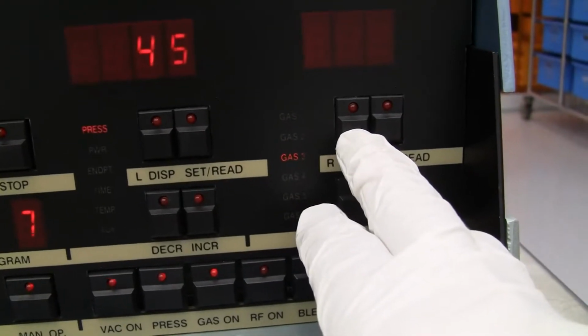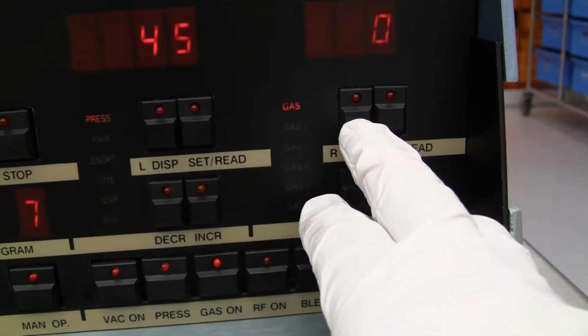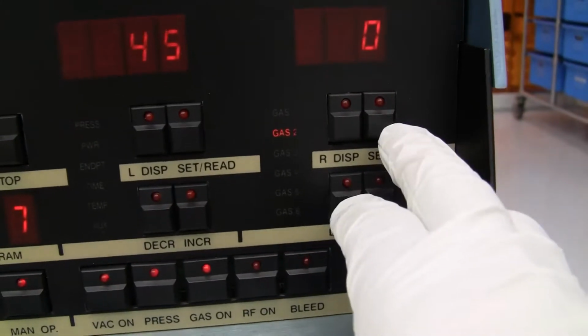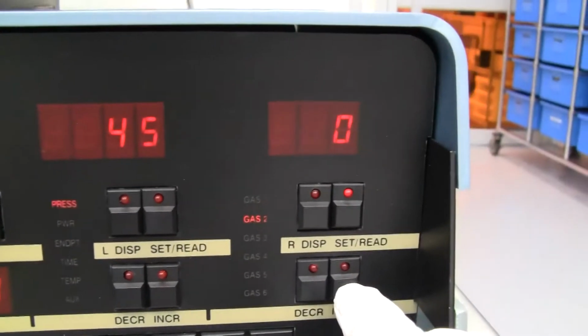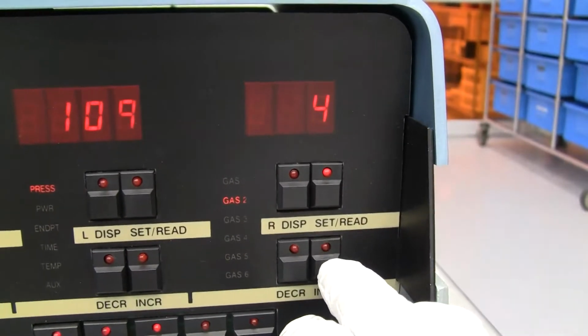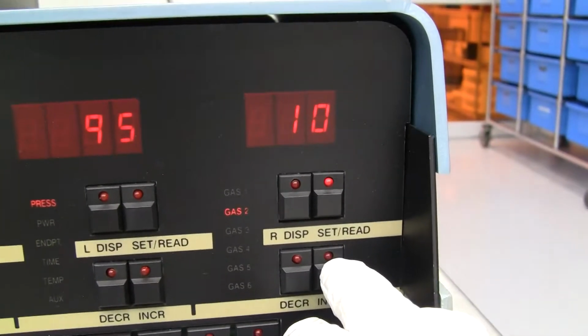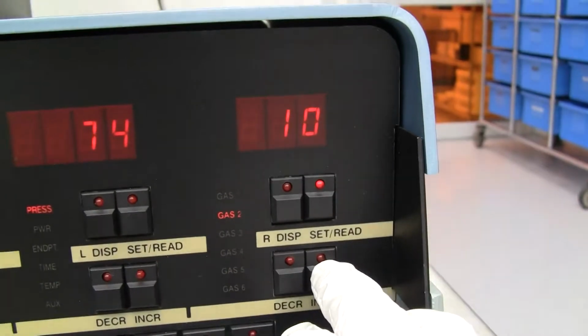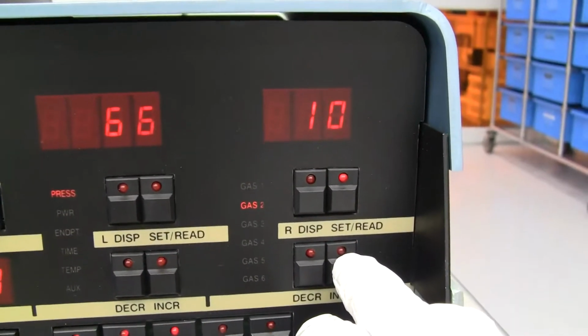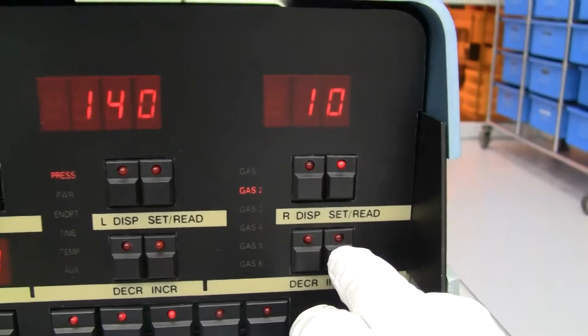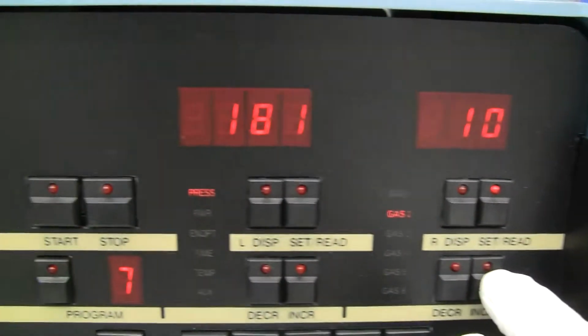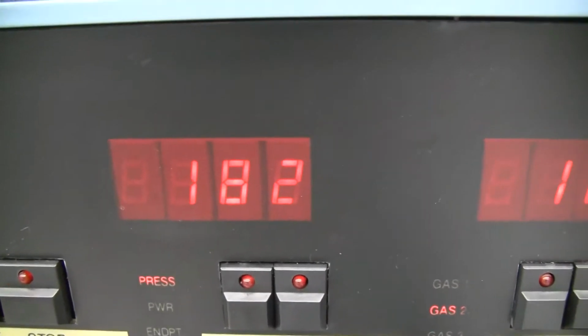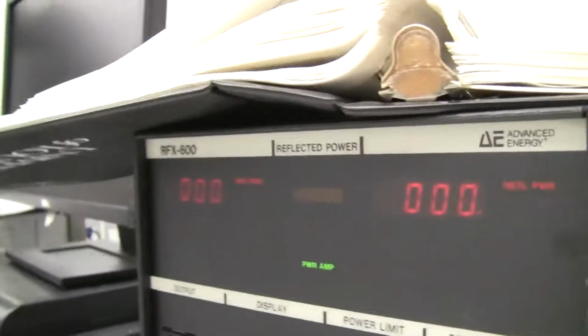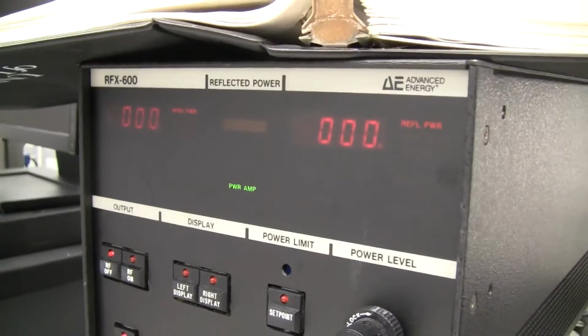Just to show you, let's see, let's play some games here. So, let's put in some oxygen. Currently set to 0% of full scale. So I'm going to go ahead and put 10% of full scale, which I think is about 250 SCCM calibrated to nitrogen. You can see our pressure starting to come up. 182 millitorr right now. Got no plasma on. No plasma.